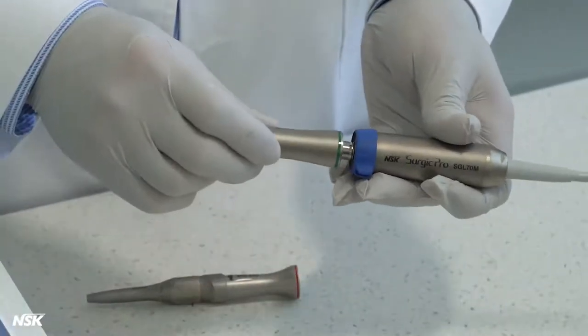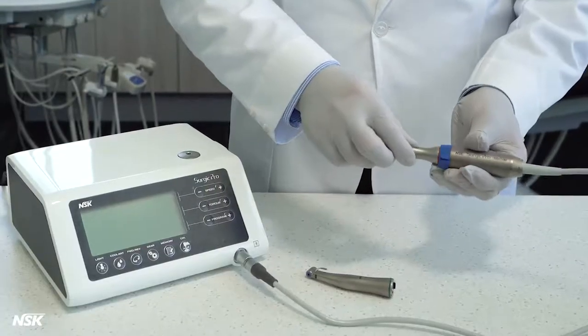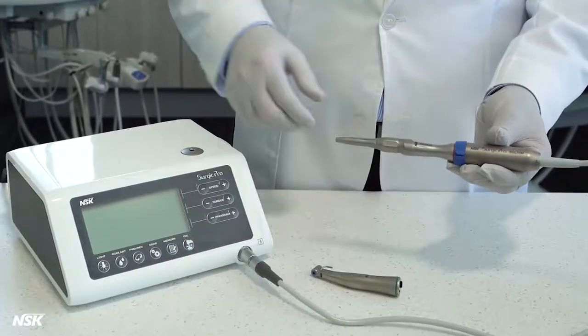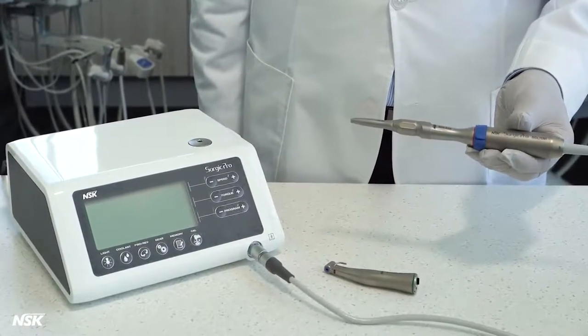Insert the attachment into the motor and twist until it locks in place. Non-optic attachments do not need to be twisted to be locked in. However, microsurgery handpieces will need to be twisted on non-optic motors to be locked in place.